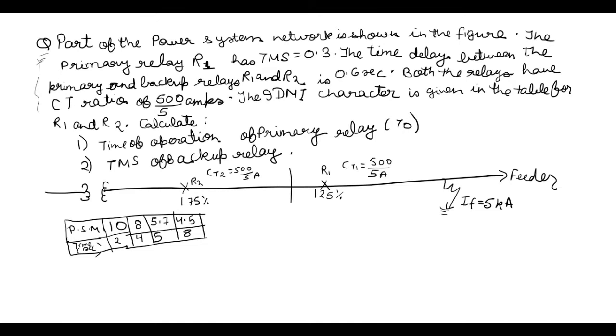Part of the power system network is shown in this figure. The primary relay R1 has TMS value 0.3. The time delay between R1 and R2, means primary and backup relay, TD is 0.6 second. Both of the relays have CT ratio as 500 to 5 amperes. The IDMT character is given in the table for R1 and R2. Now this was the character which we were unable to understand, and I will show you how to use this. You have to calculate the time of operation of primary relay T0 and TMS for backup relay.